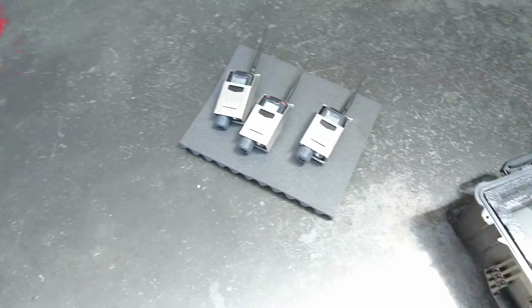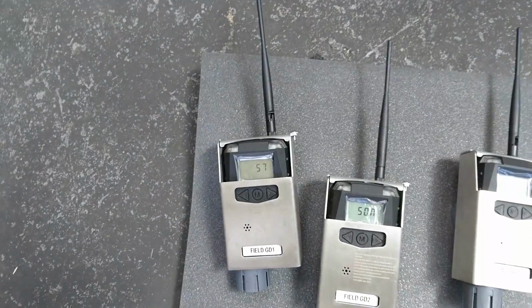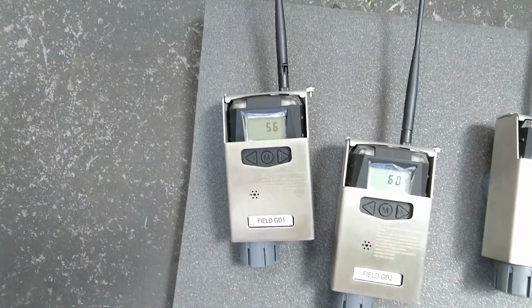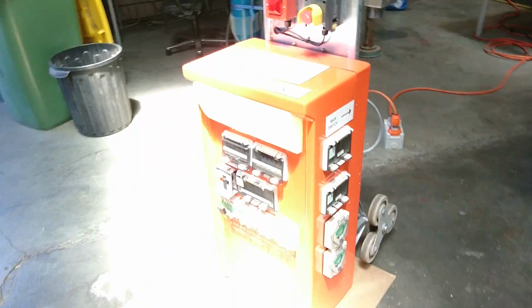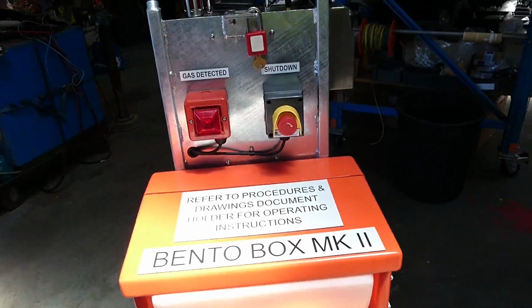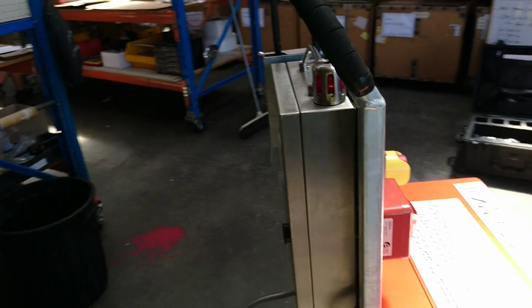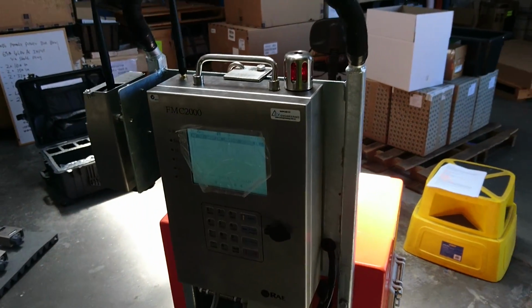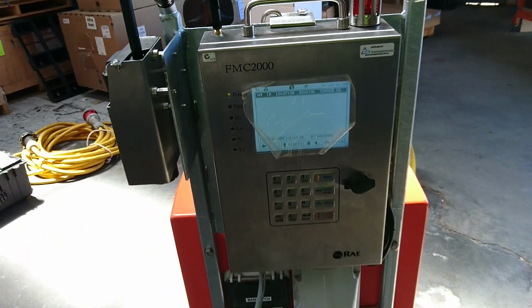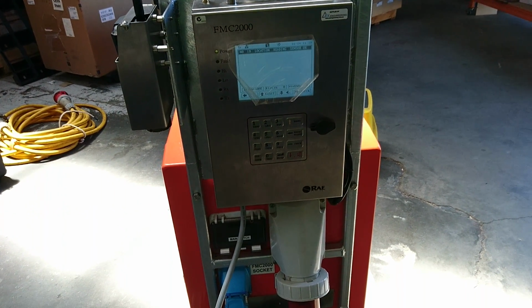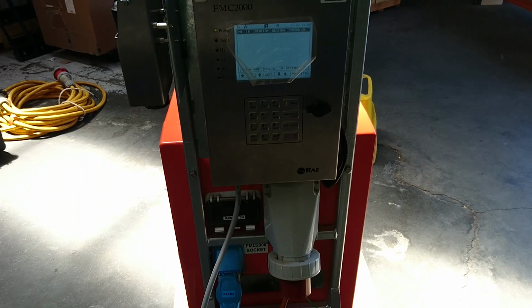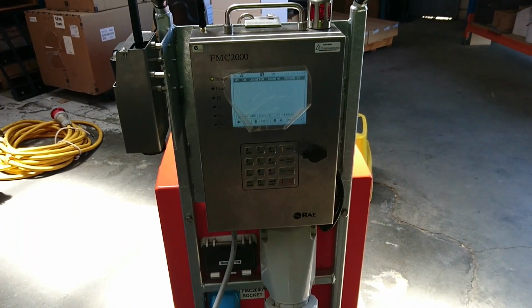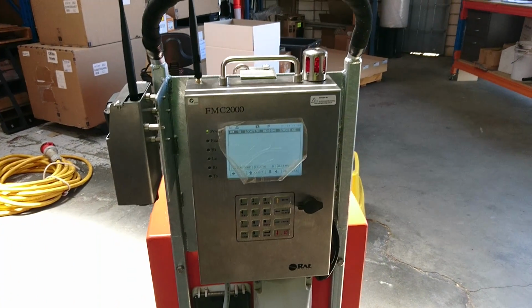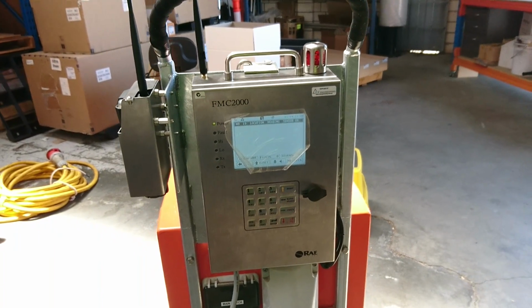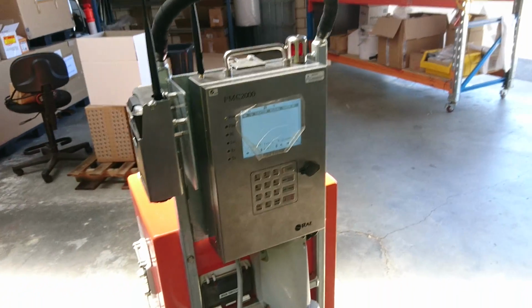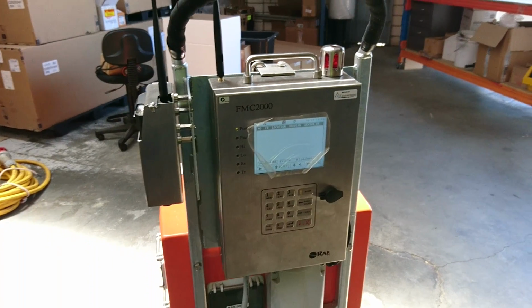Okay, so they take about a minute to start up. So the way the receiver's programmed is once it's powered up and you start connecting devices to it, if you, let's say, connect 2 devices and then one of them drops out because the battery goes dead or it goes out of range, then the FMC will cut power to your output devices.